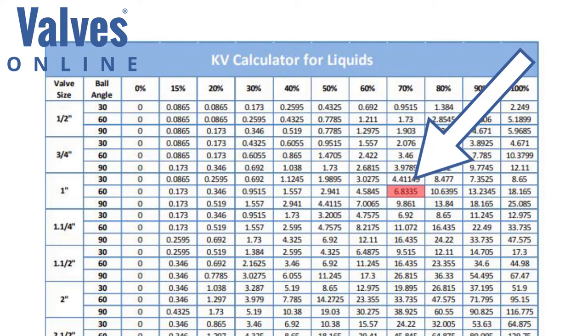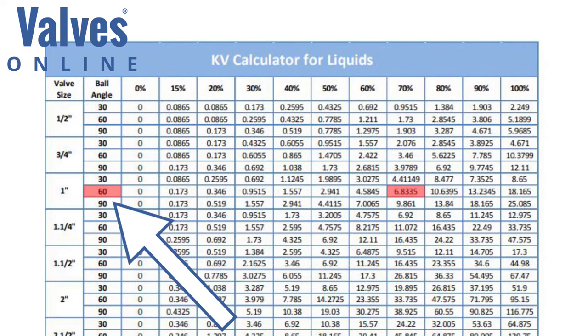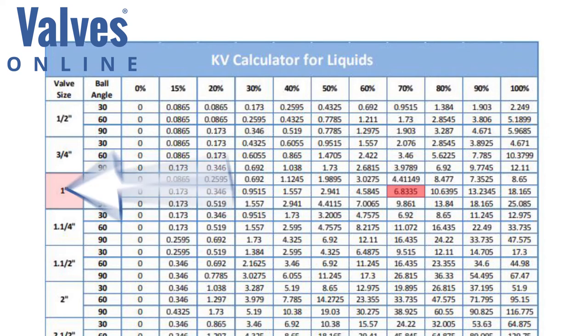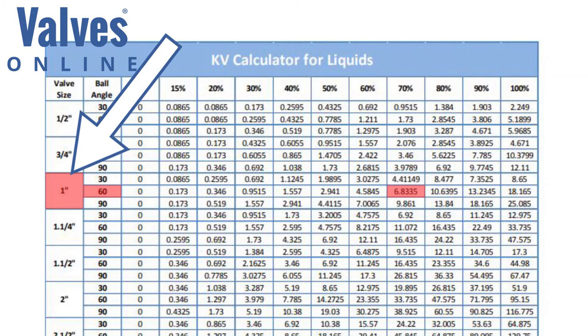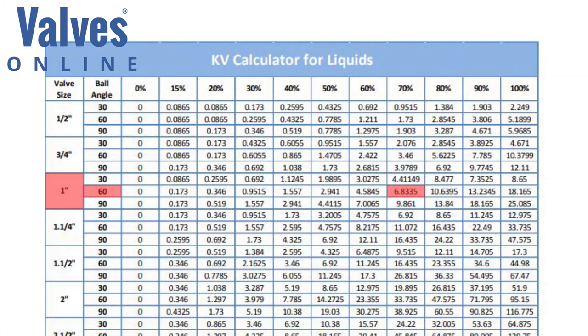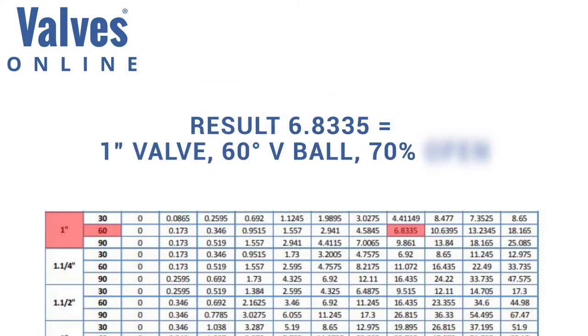Looking closely, we see the figure of 6.8335 coincides with a 60 degree V sector ball at 70 percent open, which isn't on the top end. The result: 6.8335 equals a one inch valve with a 60 degree V ball at 70 percent open. The valve can now be selected on the product page using the drop down.